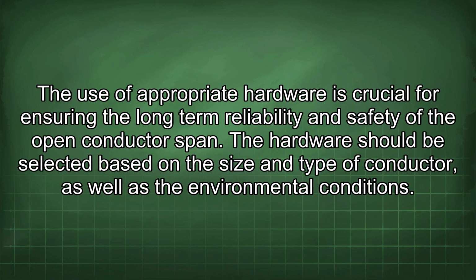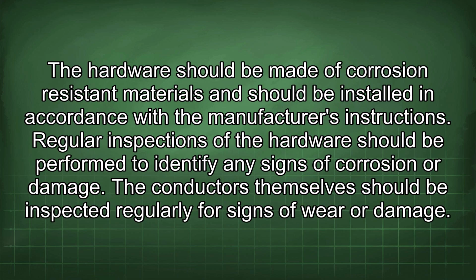The use of appropriate hardware is crucial for ensuring the long-term reliability and safety of the open conductor span. The hardware should be selected based on the size and type of conductor, as well as the environmental conditions. The hardware should be made of corrosion-resistant materials and should be installed in accordance with the manufacturer's instructions. Regular inspections of the hardware should be performed to identify any signs of corrosion or damage.